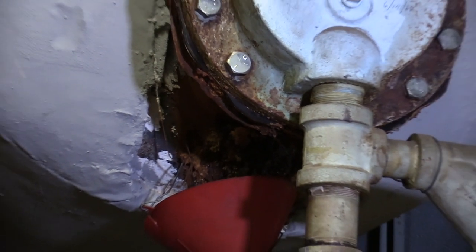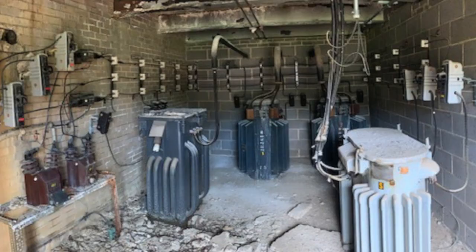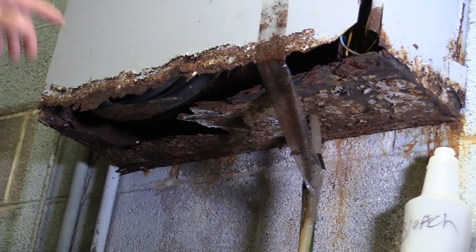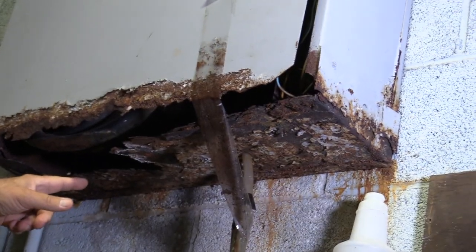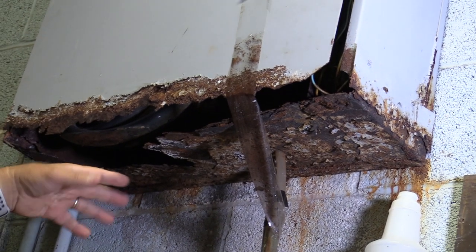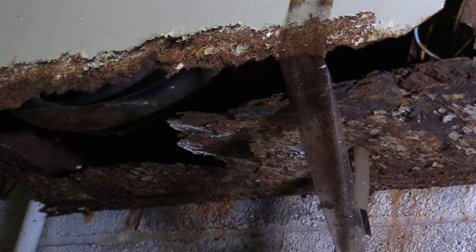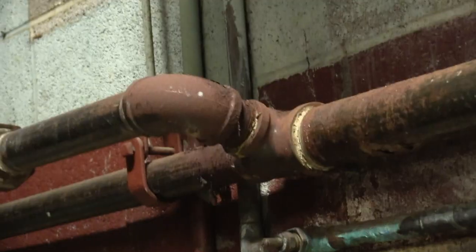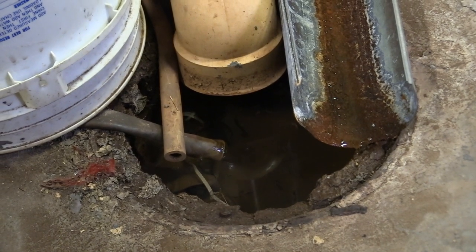This is the underground electrical — it goes out to the 1966 addition, coming from the main over here, through the transformers, and across. But there have been leaks in here, and to fix it would probably be $50,000–$60,000 just to stop the leaking, because the pipes that go underground to the 1966 addition by your office are leaking and have actually deteriorated this junction box — and it just leaks right down the drain.